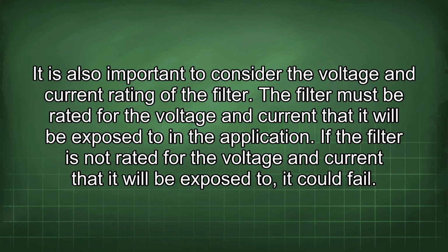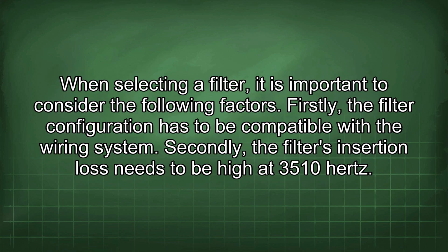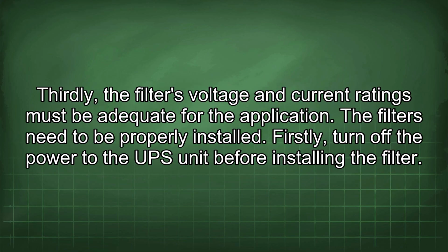It is also important to consider the voltage and current rating of the filter. The filter must be rated for the voltage and current that it will be exposed to in the application. If the filter is not rated for the voltage and current that it will be exposed to, it could fail. When selecting a filter, it is important to consider the following factors. Firstly, the filter configuration has to be compatible with the wiring system. Secondly, the filter's insertion loss needs to be high at 3510 Hz. Thirdly, a filter's voltage and current ratings must be adequate for the application.